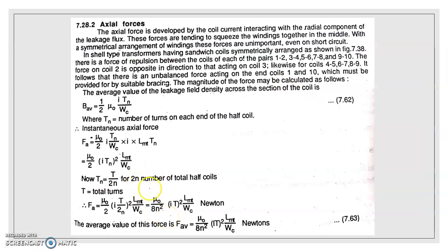Let's see the axial forces. About the axial forces, just by observation, as I defined earlier, they are developed because of the interaction of the current and the radial component of the leakage fluxes. These forces are unimportant under a symmetrical arrangement of the winding.